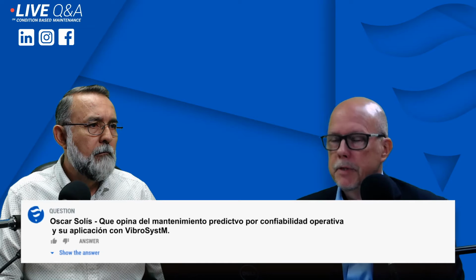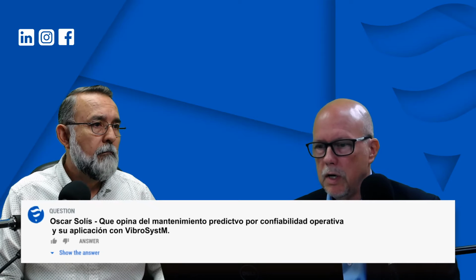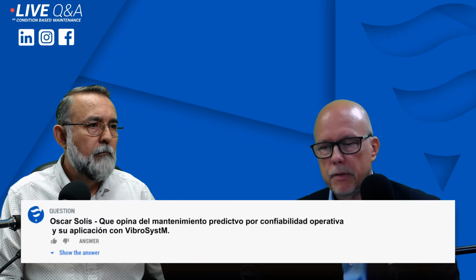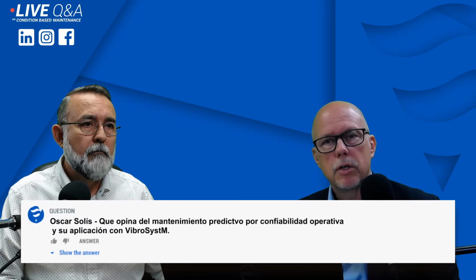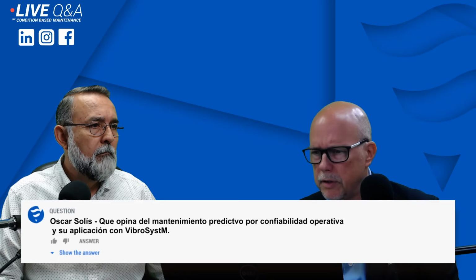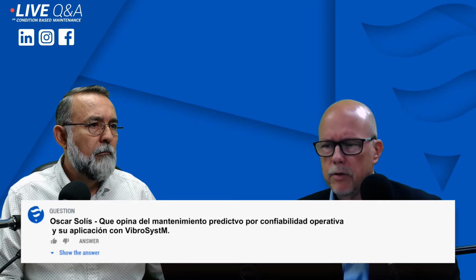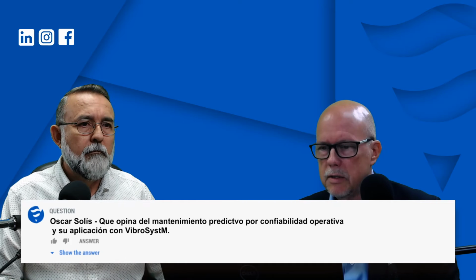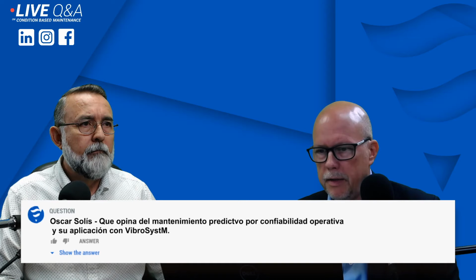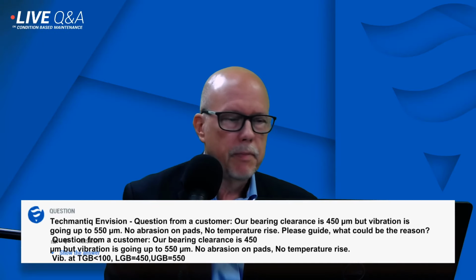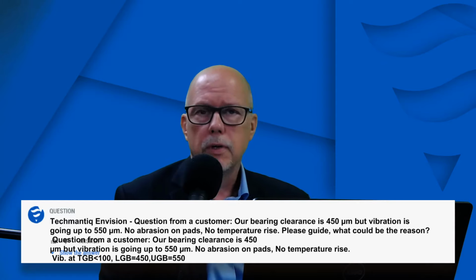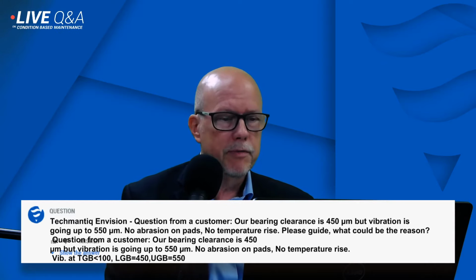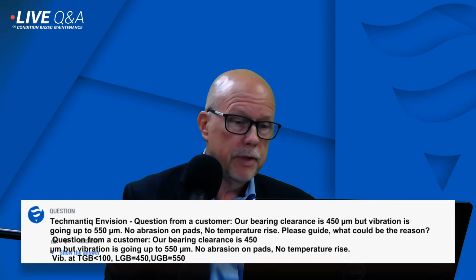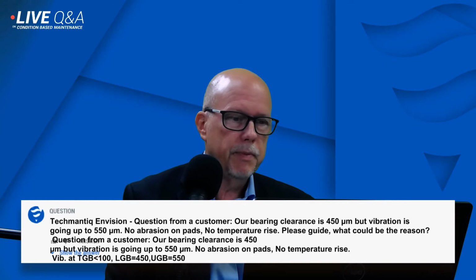We had a question from Techmantiq Envision, and the question was, our bearing clearance is 450 microns, but the vibration actually goes up to 550 microns in certain conditions, if I remember correctly. They found no abrasion on the pads, there's no temperature rise. What could be the reason? They mentioned that, again, the clearance is 450 microns, but the vibration at the turbine is 100 microns peak to peak, which is excellent. But the lower guide bearing, just below the rotor, the vibration values are actually 450 microns peak to peak. And above the rotor, they're 550 microns peak to peak.